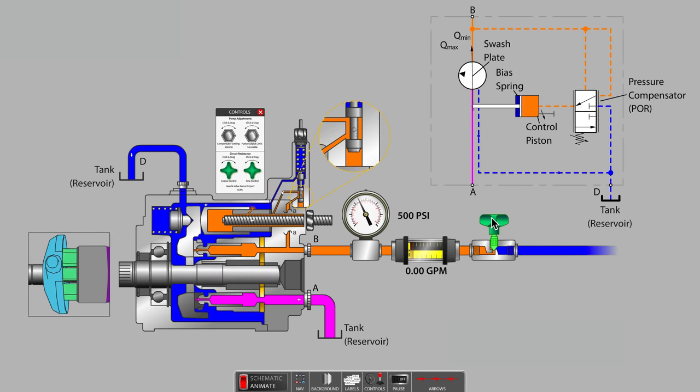But since the needle valve is still closed and there is no flow path available, system pressure quickly reaches the setting of the pressure compensator spring and the control piston once again moves the swashplate towards the zero degree angle where no pump outlet flow occurs. The action of the pressure compensator is essentially maintaining a constant pressure.